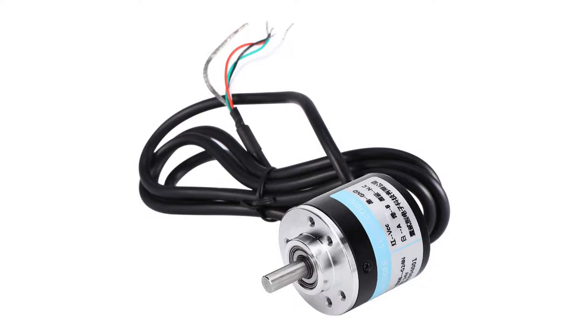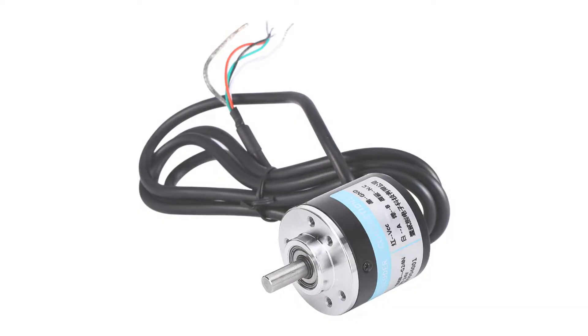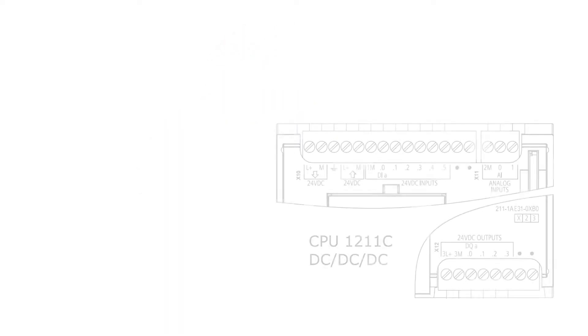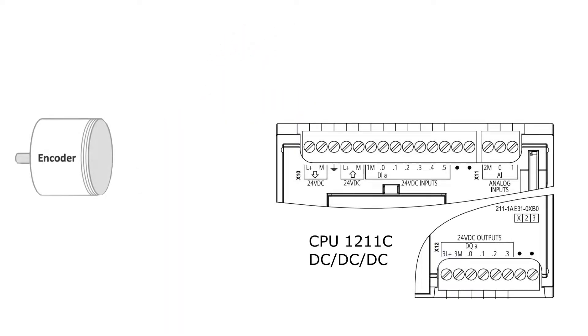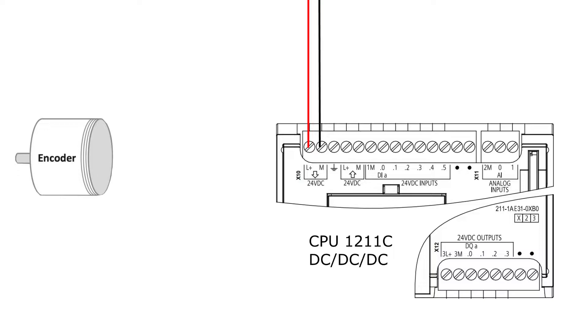Let's first go through the wiring of the encoder. First, we will need 24-volt DC to power up the PLC. Depending if we use a PNP or NPN encoder, we will need to either connect 24-volt-plus or 0-volt-minus to the 1M terminal.